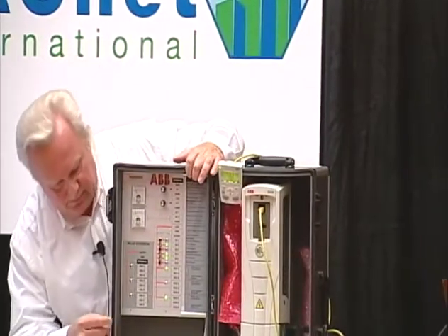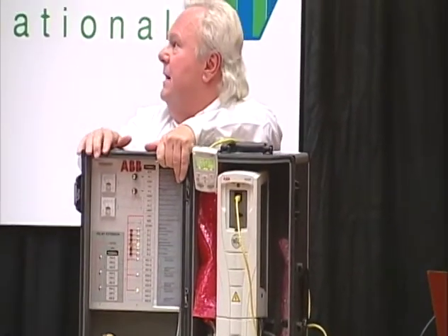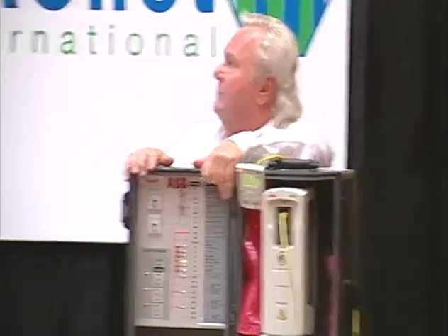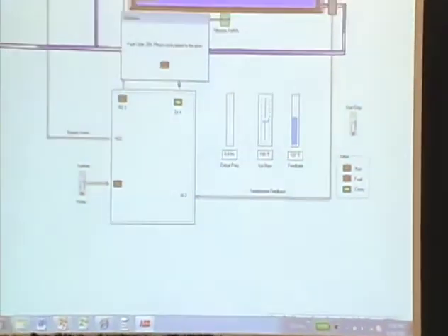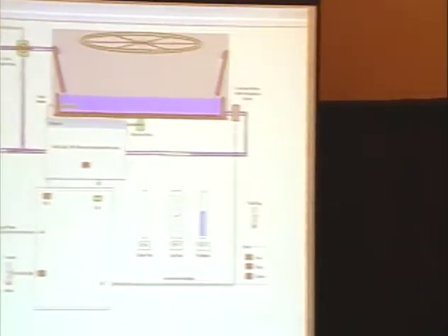I'll quickly launch another one to show you some of the power with this one, if my eyes will work. Is there someone says cooling tower there? Second one? And now I'm launching an application for a cooling tower. In this case, I got to close digital input 4 and open the rest. So in this case, there's a tremendous amount of automation built in here. And for a cooling tower application, I don't really need an energy management system. It's all built into the drive.